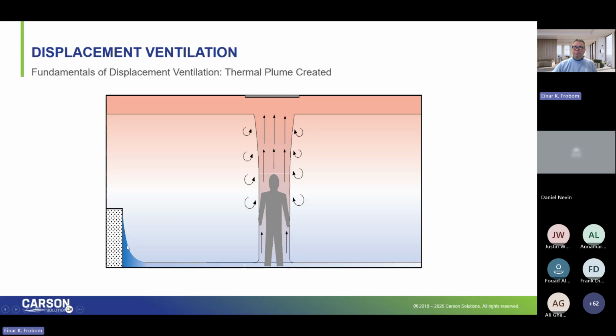So displacement 101: the diffuser is in the classroom. And as that supply air comes out of the diffuser, it's about 63, 65 degrees. So it's slightly cooler, slightly more dense, and it drops to the floor. But it has some momentum, some velocity force until it comes in contact with the student, at which point the student's body temperature increases the temperature around it, increases the buoyancy, and you create this tight thermal plume that lifts the fresh air or reconditioned air up to the breathing zone. So the path from the diffuser to the breathing zone is much more effective in this method than delivering air where people aren't, hoping it gets distributed down, picks up contaminants, and then comes to the occupant.